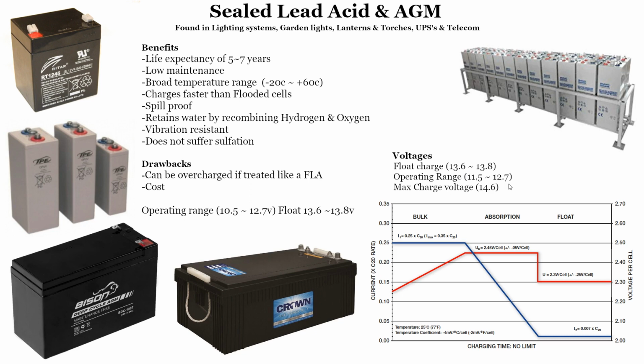The voltage range on these guys is from 11.5 to 12.7. 11.5 is what you should consider a dead battery. So if you're talking a 24-volt system, that would be 23 volts, and if it gets down to 23 volts, that is bad. The upper operating range is 12.7, so that would be 25.4.